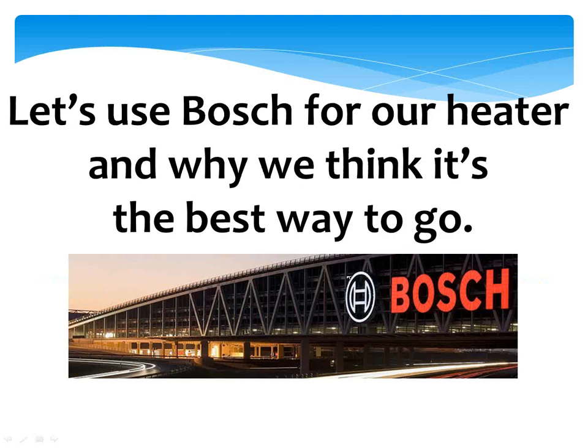One of the best things about the Bosch, there's a lot of things I liked about it, and one of the reasons why we kind of started dealing with them, is they do actually make something that's ASME rated because they take it to 225,000 BTU. If you see up in the upper right-hand corner, that little C, on their model designation, C means condensing. The 1210 is actually 12.1 gallons per minute at something really stupid temperature rise, nothing. Basically, if you're down in Florida and it's 100 degrees and the thing's out in the carport. But the C at the very end is the commercial version.